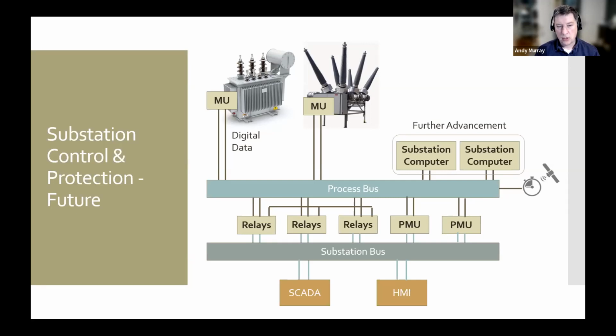It can do this not only at the speed that these relays expect, millisecond resolution, but it can also determine what it calculates the value should be based on the rest of the values it knows are good, and substitute in that value. This could be most common when the device is failing, where the transducer or device out there creating those amps or voltages is failing.